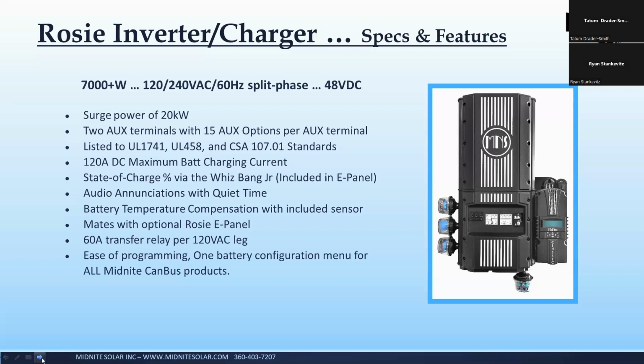One thing the Rosie does, and all the new equipment does, is it actually uses a battery temperature sensor for more than just compensation. So if you've got a lithium battery, we can tell it to stop charging at this temperature if it gets cold, or stop charging at this temperature if it gets hot. So we have a lot more programmability around that battery temperature than just compensating the voltage, like we're used to on lead acid batteries. So that's all built in. And we talked about the E panel. We'll get to that in a minute.